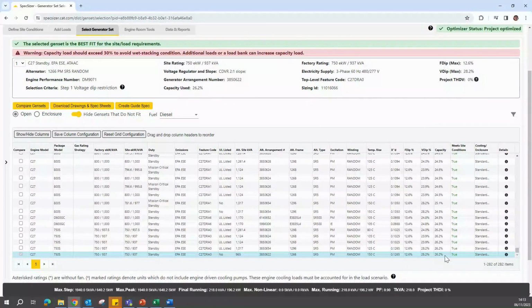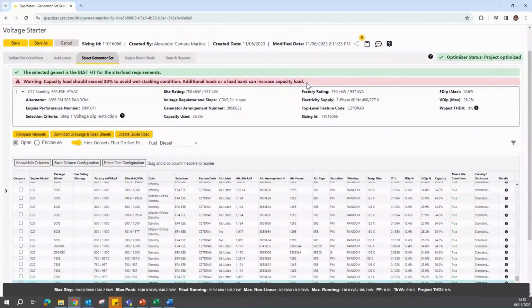We can see it's using only 26.2% of its capacity. This situation is not good. It means the engine will struggle to reach proper operating temperature, which can lead to a wet stacking condition, as you can see in the note at the top of the page. This is going to have a negative impact on the engine life. A sizing like this is often a result of motor starting requirements that far exceeded the running load.